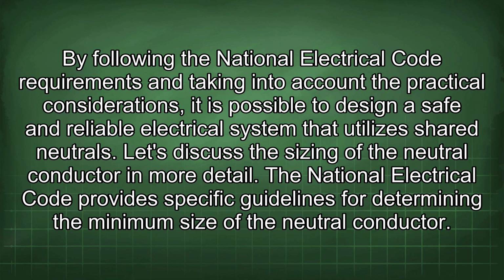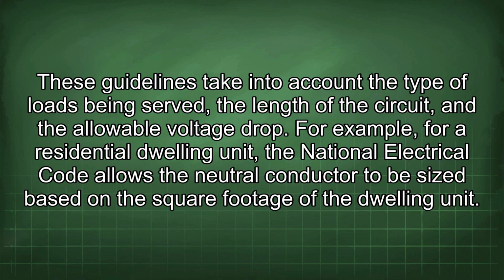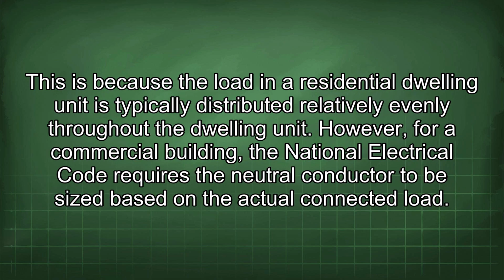Let's discuss the sizing of the neutral conductor in more detail. The National Electrical Code provides specific guidelines for determining the minimum size of the neutral conductor. These guidelines take into account the type of loads being served, the length of the circuit, and the allowable voltage drop. For example, for a residential dwelling unit, the National Electrical Code allows the neutral conductor to be sized based on the square footage of the dwelling unit. This is because the load in a residential dwelling unit is typically distributed relatively evenly throughout the dwelling unit.